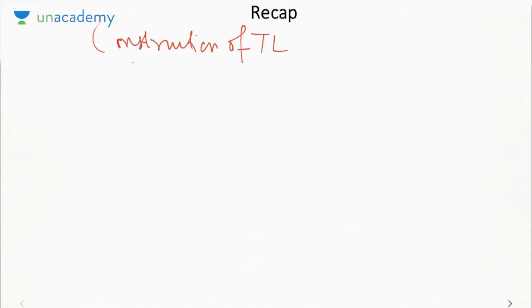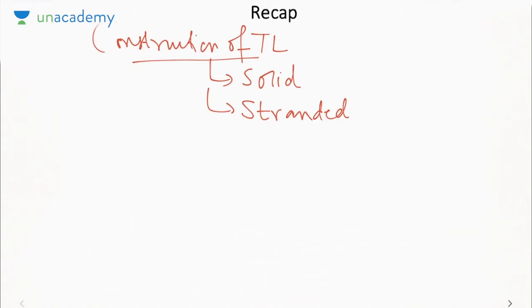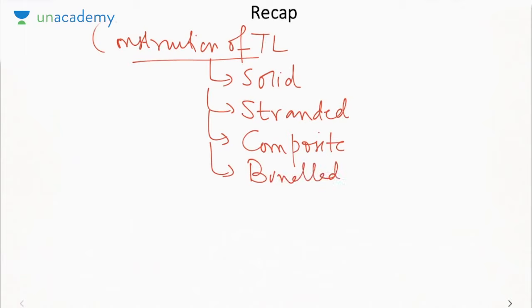Okay, there we saw there are four types of conductor. Solid conductor, which had the problem of skin effect. Then we moved to stranded conductor, which reduces skin effect, but there are problems of corona and strength. Then we moved to composite stranded, in which we saw the ACSR type of conductor, and then we moved to bundled conductor, which reduces the corona. We also derived the parameters.